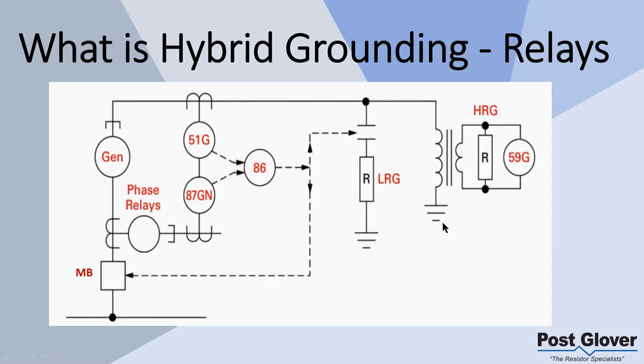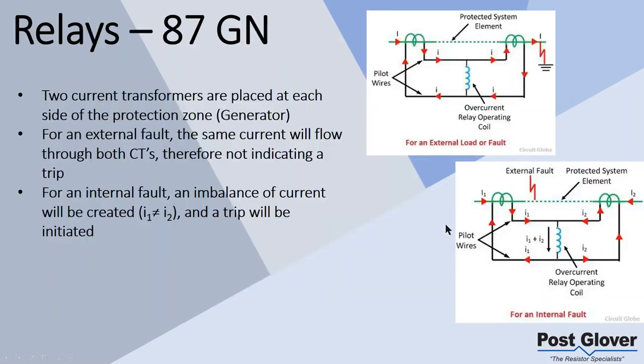So I'm showing you what it is at this point. Obviously we'll talk about why here in a second. Let's go over, just if you haven't seen this before, differential relaying, just to give you an example. Essentially, you're talking about current inputs or current detections at both sides of your protection zone, usually each side of your generator.